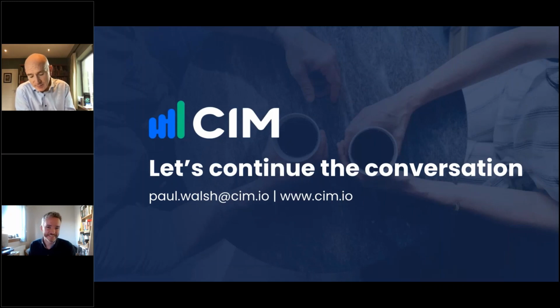Yeah, it's a very good point. We see that issue with naming conventions every day of the week. What it does, from our perspective, Dan, is make the commissioning of the site longer for our engineers. Internally, we've developed an artificial intelligence algorithm that searches all the points, looks for things like AHUs, VAVs or FCUs, and does meta tagging on those tags to speed that process up. Now, you're right. You go into one site and it's called AHU 0104. You go into another site, it's called air handling unit. You know what I mean?